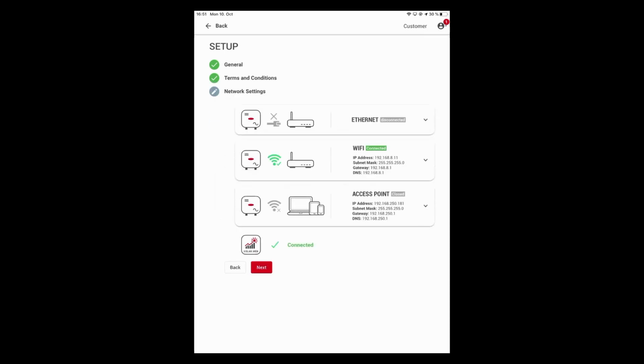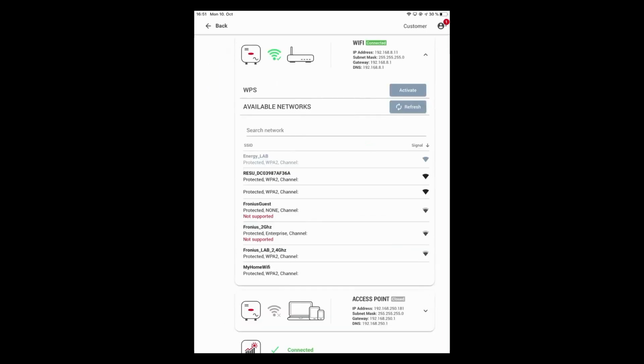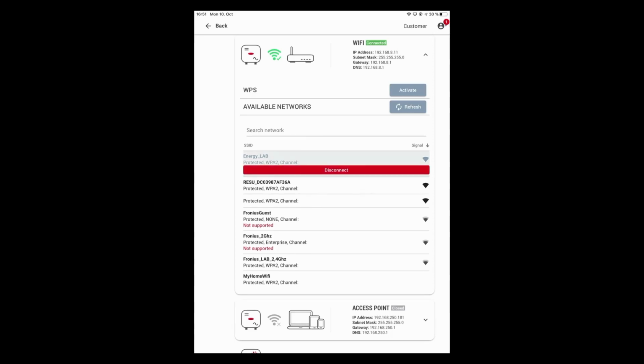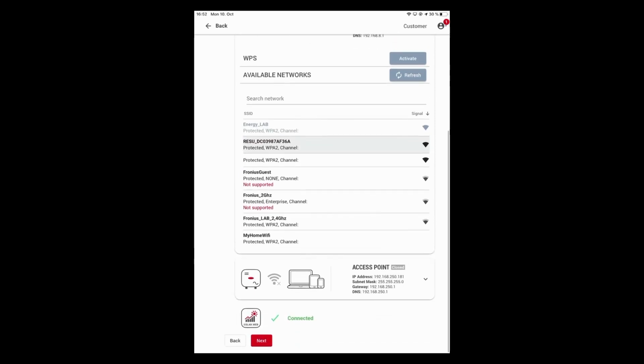Yeah, third point is then bringing the inverter online, and therefore you can choose between Ethernet and Wi-Fi. In the Wi-Fi settings we can of course choose from the list of available Wi-Fi networks, and in this case we are choosing the end customer Wi-Fi. So for example, the network that you will find at the end customer's place where you want to connect the Gen24, and then you just type in the Wi-Fi password that you get from the end customer to connect the Gen24 Plus with the local network.